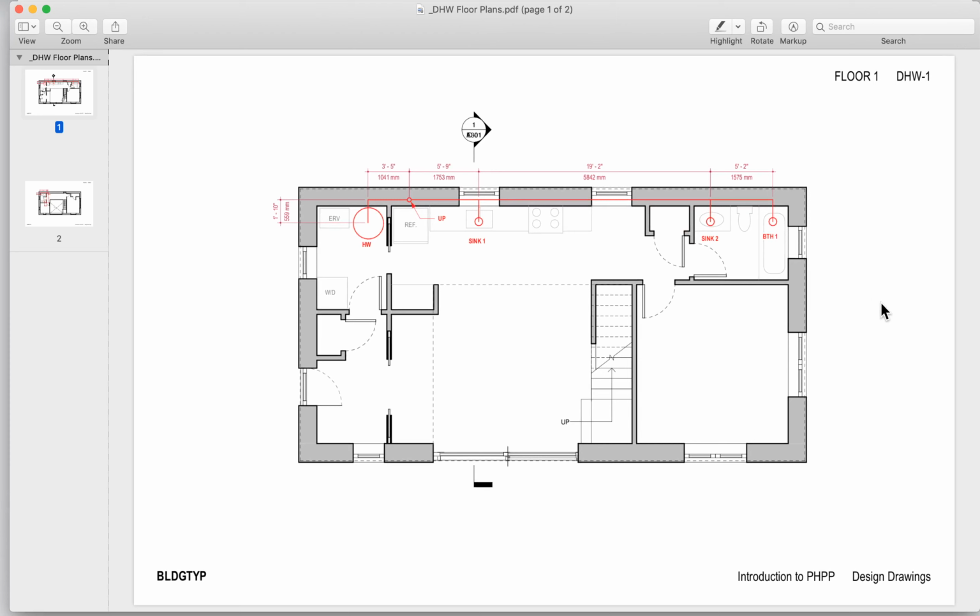We just put this together as a sort of schematic level diagram of the plumbing for the building so that we can talk about how we're going to model it. Now, for this building, as a very small building, I don't think we need a recirculation system. We could discuss it. Maybe you think we need a recirc system to the upper level bathroom, but I don't think we do on a building of this scale. So in this project, to keep things as simple as possible, we're not going to include a recirculation system.